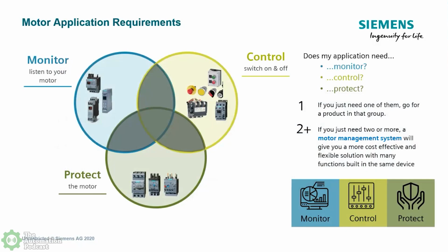So we call our motor application requirements that we're going to monitor the motor, we're going to control the motor, and then we're going to protect it. But that protection extends not just to the motor. I hope that you understand at the conclusion of this presentation that we want to protect the entire process that the motor turns. We want to protect that gearbox or that fan or that pump and be able to give diagnostics to help those who are using that equipment to react quickly and know what they need to do to get it back up and running or to prolong its life, in maintenance applications and preventive maintenance applications and so forth.